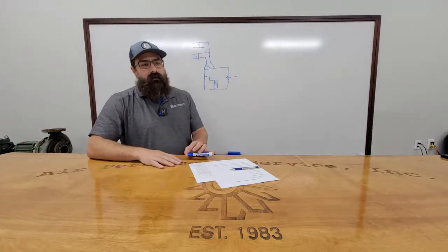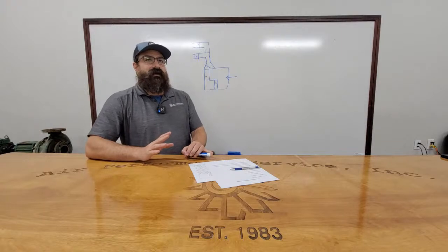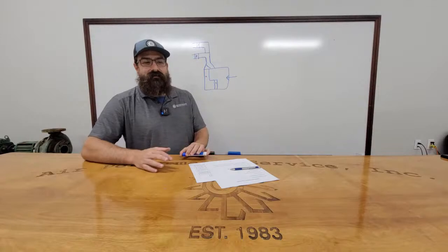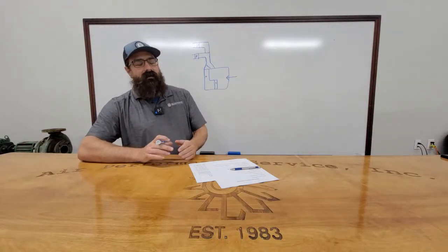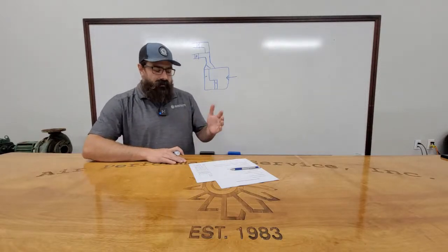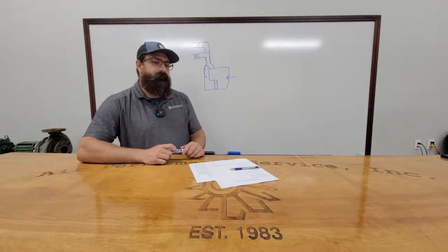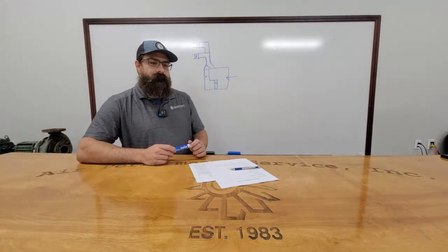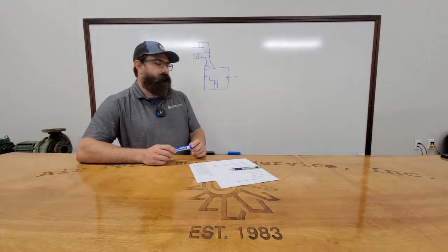And it actually doesn't have any kind of economization algorithm at all. So when I was talking about that, it's actually a bad reference, but it's purely based on CO2. It's got a 1200 CFM minimum and a 3000 CFM max. I don't remember exactly what the numbers are, but it modulates based on the CO2 demand of the building or the floor itself. I've seen your bigger mushroom fans on drives modulate too. If your limit is 2000 but you're around 1700, they'll just start spinning nice and slow and try to drop it down under 1000.